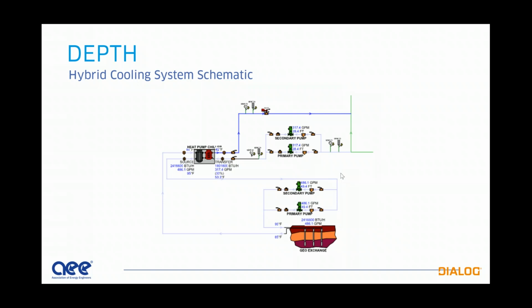Third question: how do you monitor and control inside temperature change and its effects on energy consumption and hence GHG emissions? I assume that's referring to the Calgary project. Radiant systems are controlled fairly similarly, but we leave it up to the occupants to have some control over their temperature. Typically we allow about a 3 degree Celsius range of operation so nobody can really crank their thermostats up or down. One of the benefits of radiant systems is they tend to be more comfortable. We're members of the Center for the Built Environment at Berkeley, and their studies have shown that thermal comfort in radiantly heated and cooled buildings tends to be better than in air source-based systems. So that helps people not play with the thermostats too much.